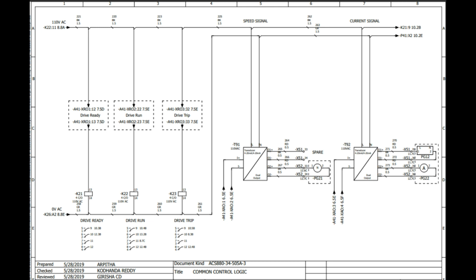For that we need isolators. Here you can see the current signal isolators, or transducer you can say, and the input is 4 to 20 milliamps. With one signal, the output will be two signals, 4 to 20 milliamps. One will go to the PLC and one will go to the field. Why transducers are used and what the importance of isolators is, there is a separate video. I'll drop the link of that video. And that is the function of the isolator: one signal will get converted into two that have to be used in the PLC and in the field.